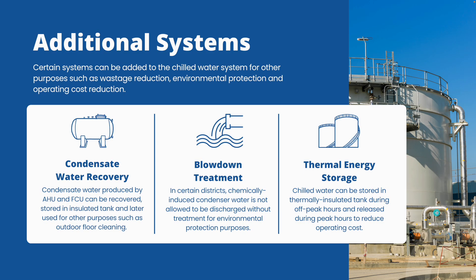Next are the additional systems — systems not necessarily required for the chilled water system to function, but needed due to specific standards and requirements. The first is the condensate water recovery system. AHU and FCU produce a lot of condensate water as they dehumidify the air. This condensate can be recovered and stored in an insulated tank, then used for other purposes such as cleaning outdoor floors, watering plants, and gardening.